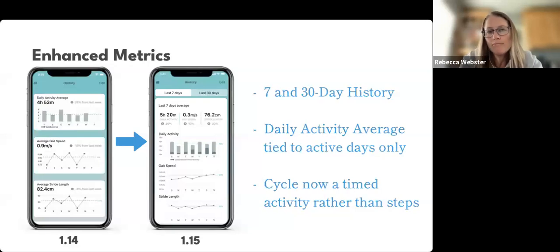First, we have weekly stats and monthly stats, so last 7 days versus last 30 days. You can see your changes over the week as well as over the month. At the top, you can also see a summary of those metrics: your activity, gait speed, and stride length, for the last 7 days or the last 30 days. Each is then broken down into daily activity, gait speed, and stride length. The daily activity has always separated out the exercise and the walking, but now it also separates out cycle for those of you who have cycle enabled. That last measure would be the activity for the cycle program.